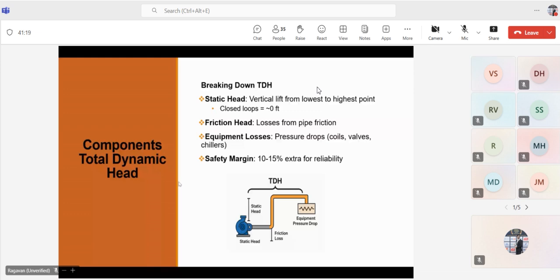Let's break down the components of the total dynamic head or TDH. The total dynamic head in the chilled water closed loop system is the sum of all the energy losses the pump must overcome to deliver the required flow rate. The slide outlines the key components. One is static head, the second one is friction losses, and the third one is equipment pressure drops. Okay, so I will explain one by one.